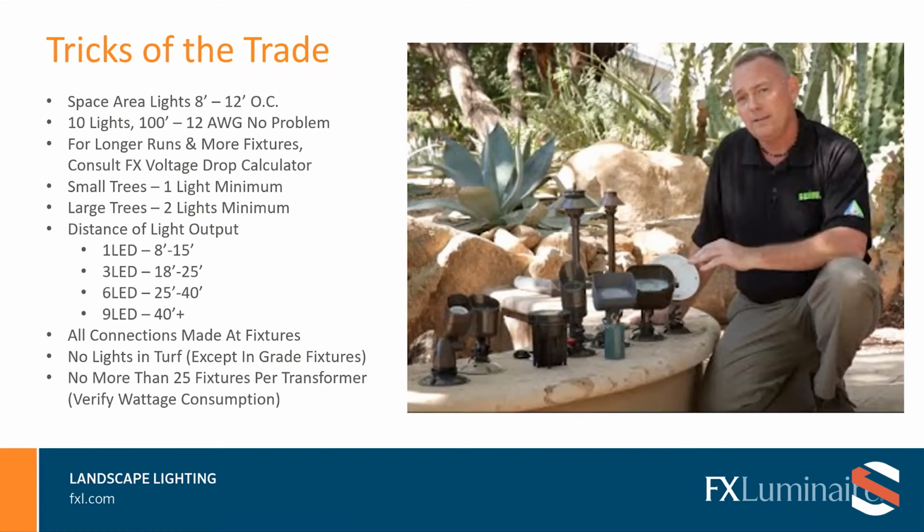Again, no lights in the turf unless they're in-grade fixtures. And then just from a good starting point, I like to do no more than 25 fixtures per transformer, because I want to verify my wattage consumption, all right? If I'm doing 25 or less, I'm like, I got this. If I'm doing more than 25, I may be able to put more fixtures on there, but I start thinking about how much power I am using, okay?